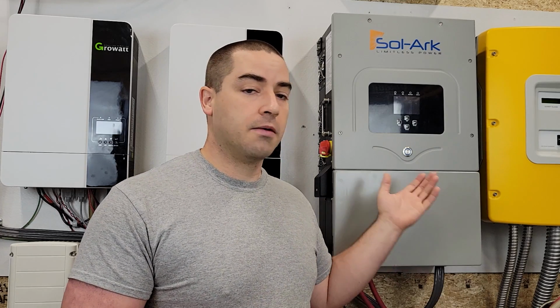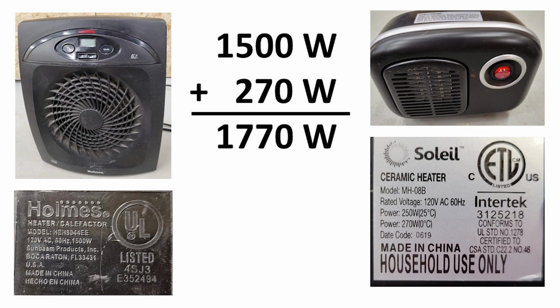I didn't want to wheel over an appliance like a table saw with a very high surge, because then I'd get comments, rightfully so, saying the shutdown happened just because of the surge. That's why I chose to plug in two small electric space heaters, which together added up to 1800 watts, because they're pure resistive loads. That way there was no surge on the system.